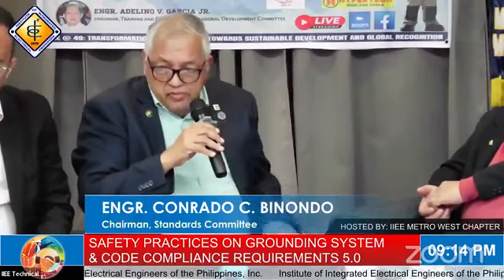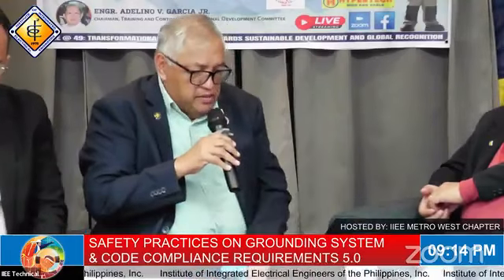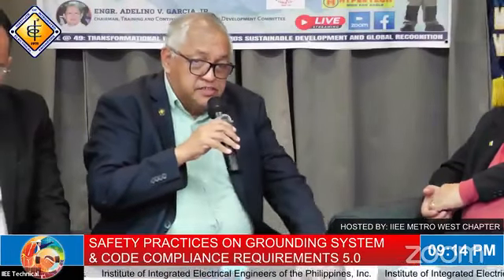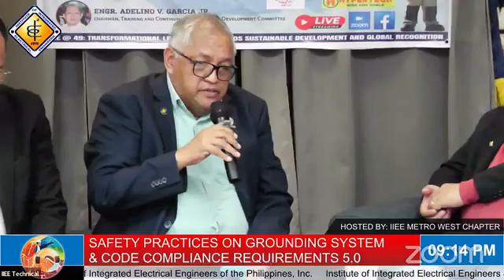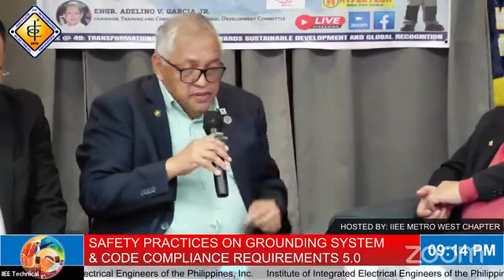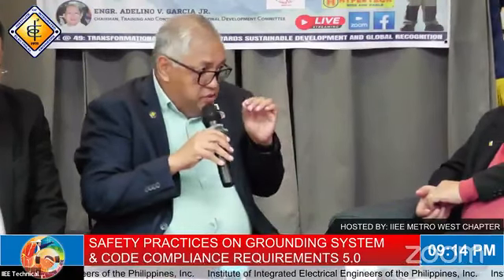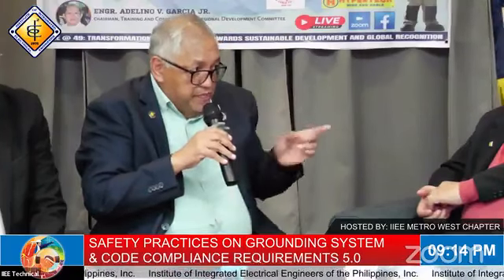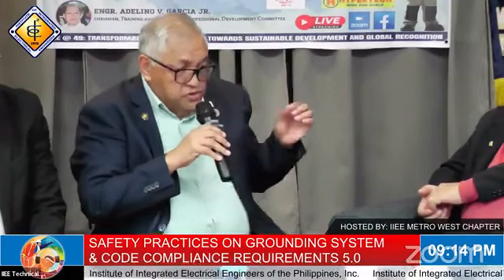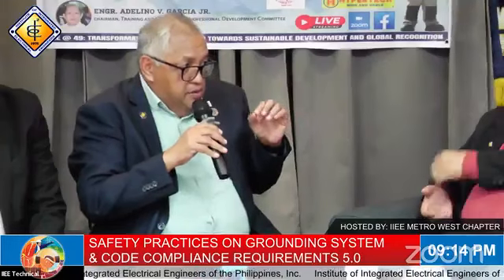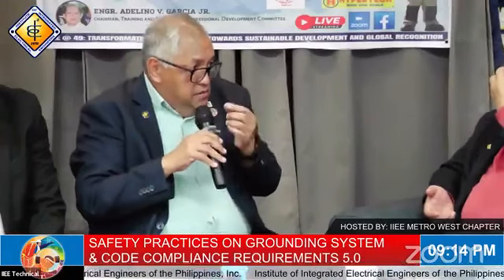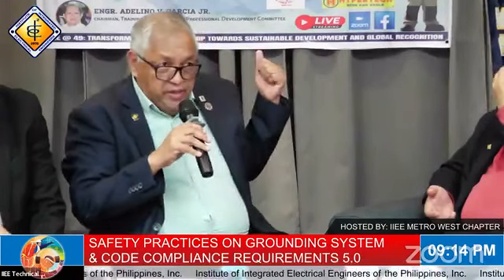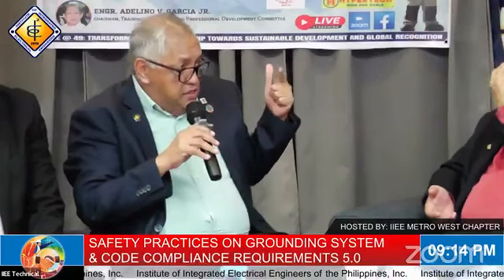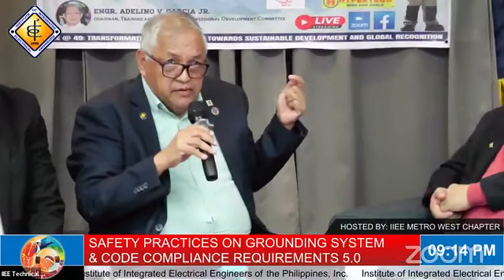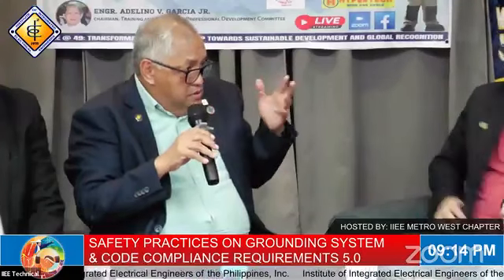Then ano ba yung tamang earthing system? Nakita natin dun sa slide sa Europe, sa Japan and any other countries, their best practice is to go on yung tinatawag na TT system. Kung makikita niyo why, because this one it will reduce yung fault current mo passing through the installation going back to the source. Mababa lang siya, not unlike the TNC na malakas, mataas, 3,500 amperes kanina, against something like 11.5 amperes in the same installation.